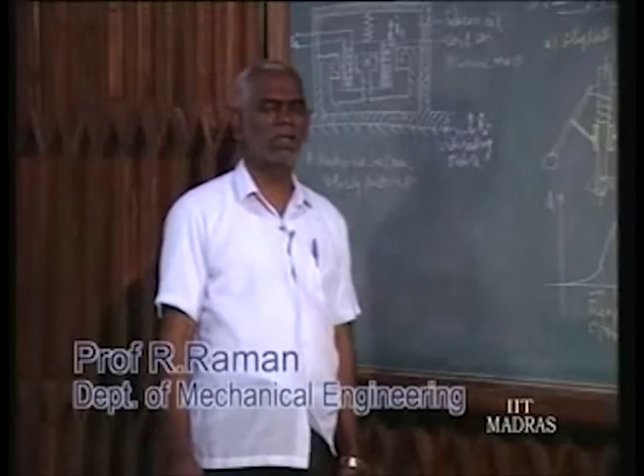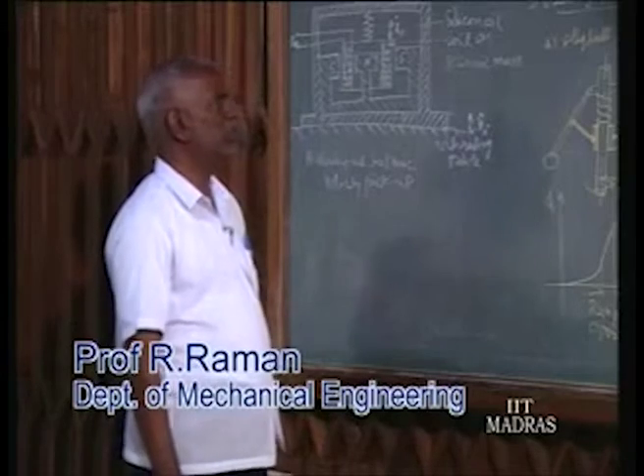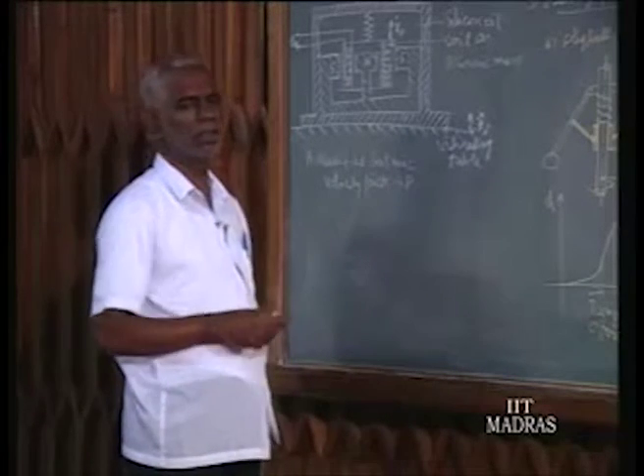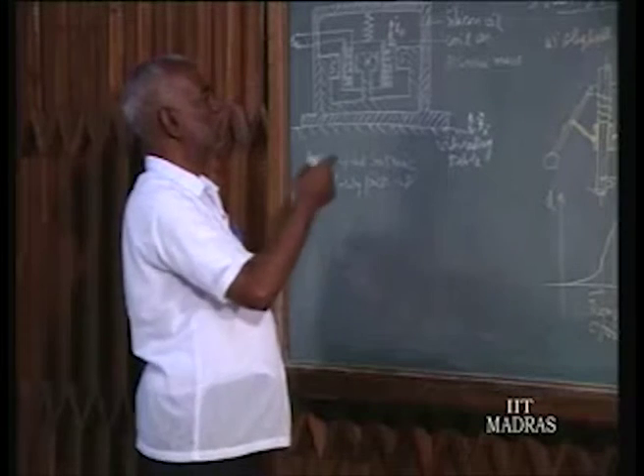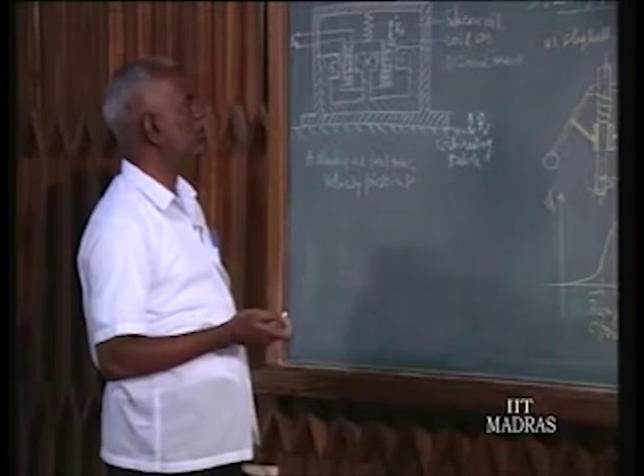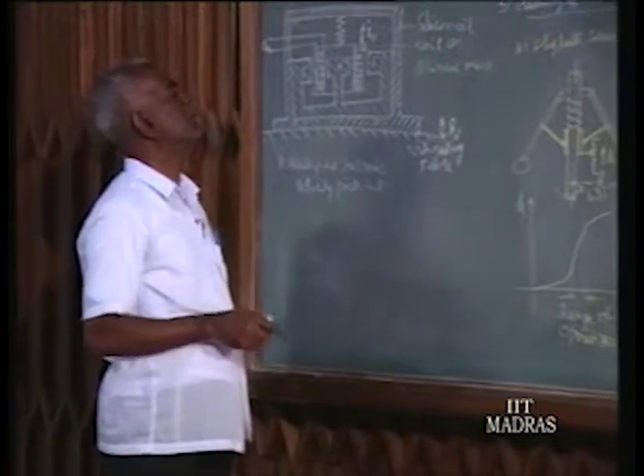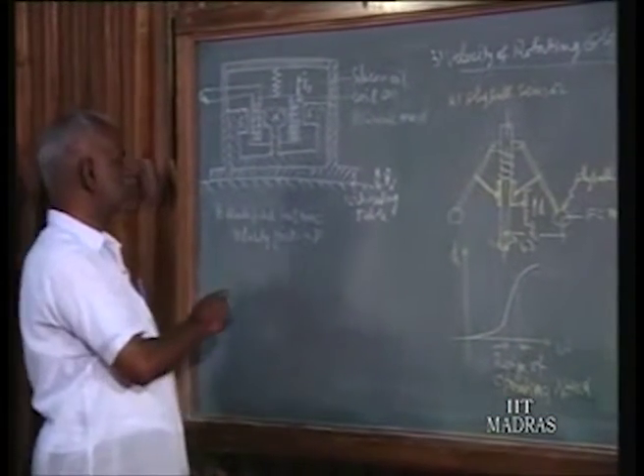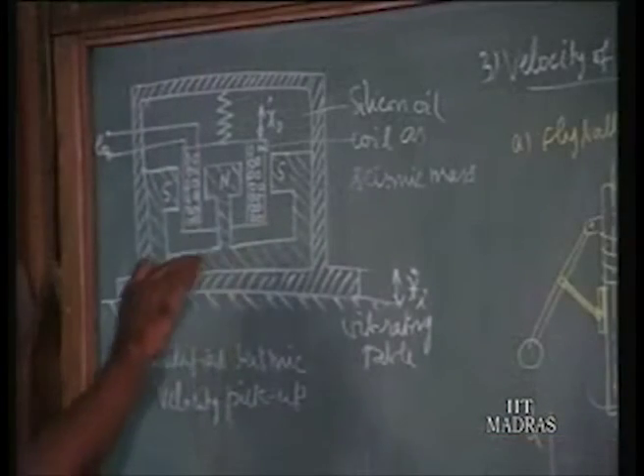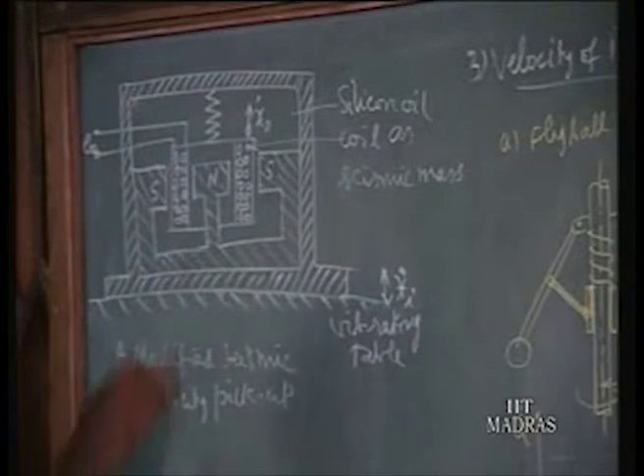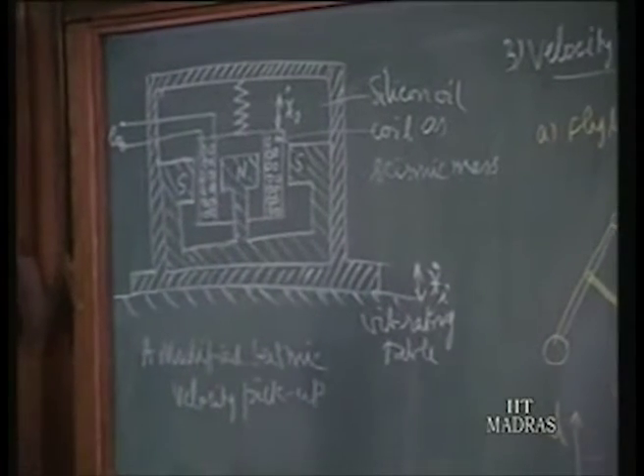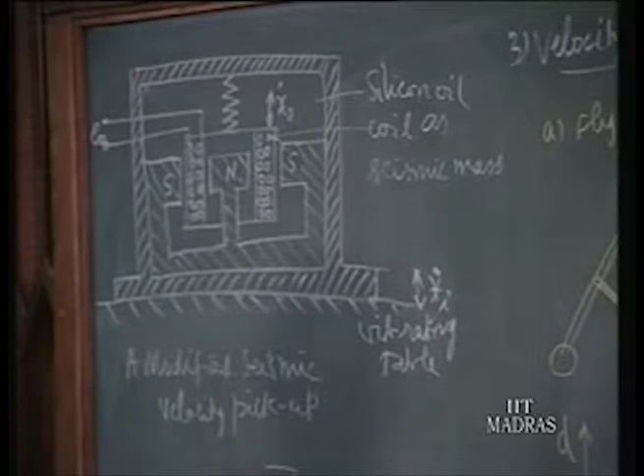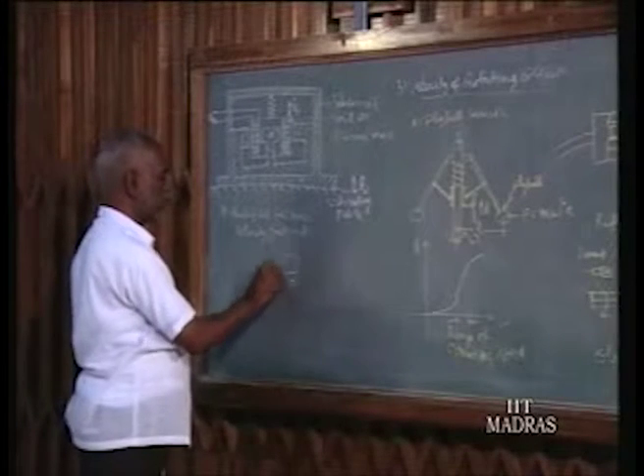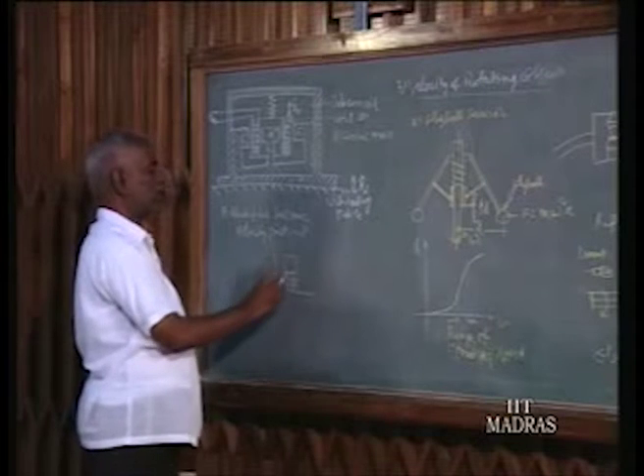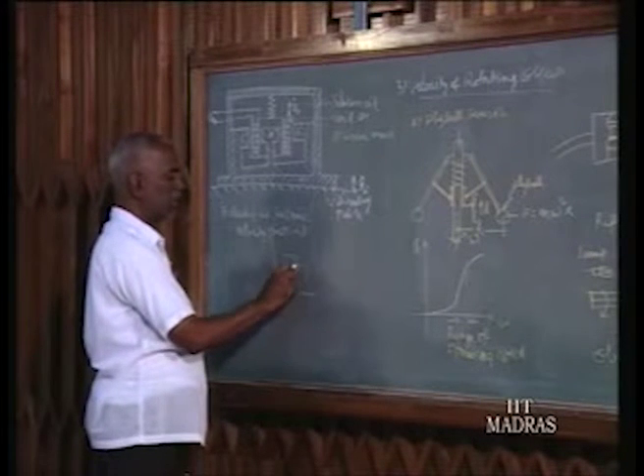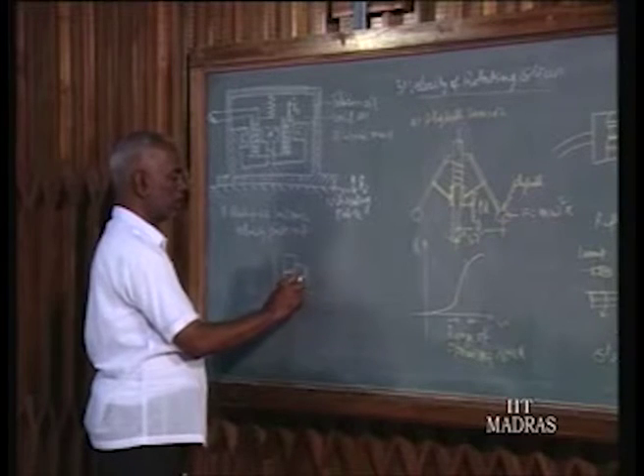For measuring reciprocating velocity, we have seen last time a seismic mass mounted over a spring and damper used as velocity pickup for the purpose of measuring reciprocating velocity. Now, this is another version, this modified seismic velocity pickup. Here the conventional mass is replaced by the coil, because in the earlier setup we had the mass here, spring, this is damper, and to measure the relative velocity of the mass we had separately the moving coil, moving magnet pickup like that.